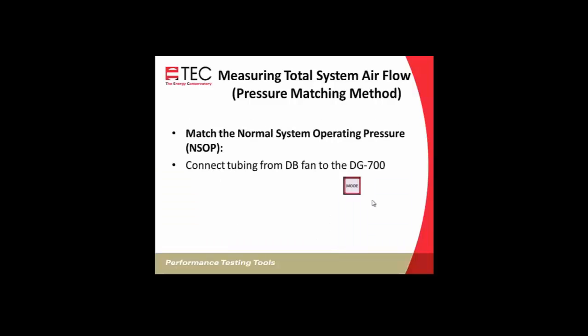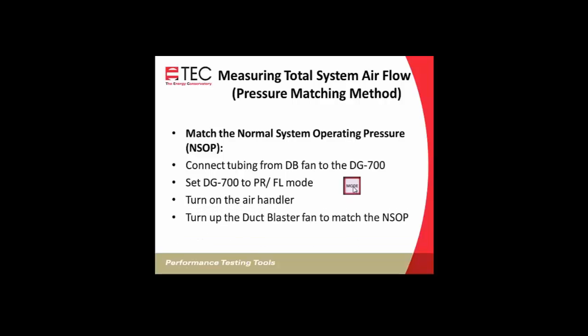So then after we've measured our normal system operating pressure and attached our fan to the system, we'll want to match the normal system operating pressure using the Duct Blaster fan. So we'll connect the tubing from the DG700 to the fan, with the channel B input on the DG700 connected to the tap of the Duct Blaster fan, and we'll set the DG700 to the pressure flow mode, pushing the mode button once. We'll turn on the air handler, and then we'll turn up the Duct Blaster fan to match the normal system operating pressure, and then record the total system air handler flow.